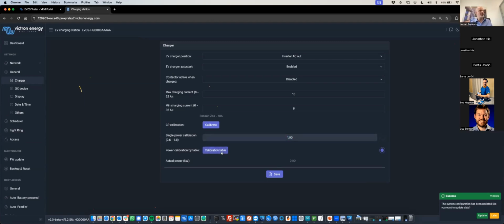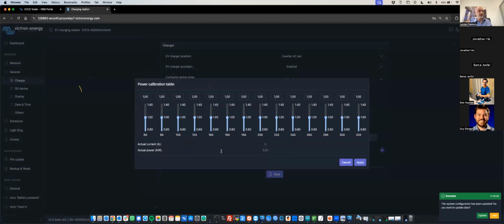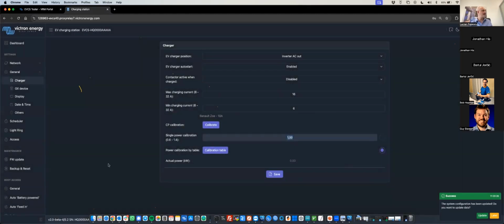Or we can have a calibration table. This will be in the new version. For each charging current in steps of 2, you can have different calibration values. For example, for 8 amps, you can have 1.3. For 10 amps, we can have 0.8 and so on. So that depends on the vehicle you are charging and the power factor for that vehicle for each current. That's for old vehicles mostly. The new ones are forced to have the power factor value to be 1. But yeah, it was requested and it is added here.